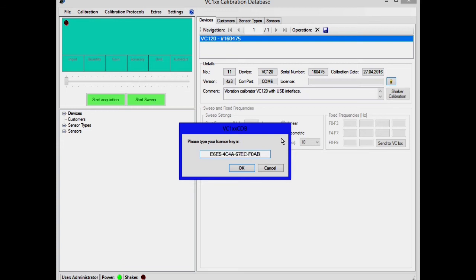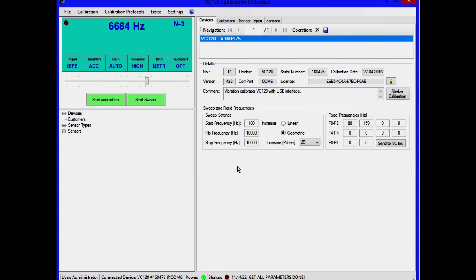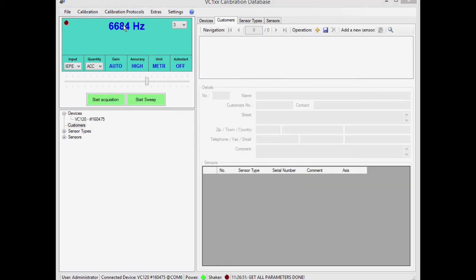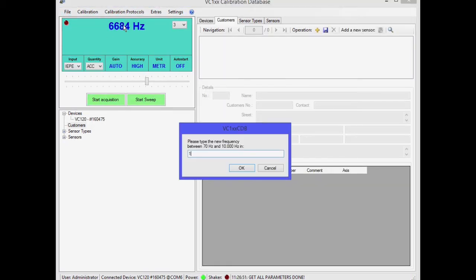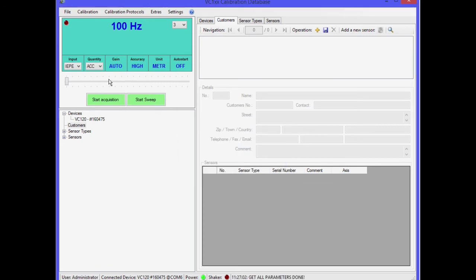When using the software for the first time, you'll need to enter the license code, which you received with your instrument. After entering the code, you'll have access to all program functions. At the top left, you'll see the control panel for manually operating the instrument. The display format is similar to the instrument's. By clicking on or moving the slider, you can set the vibration frequency. Furthermore, you can edit input type, calibration parameters, and other parameters.